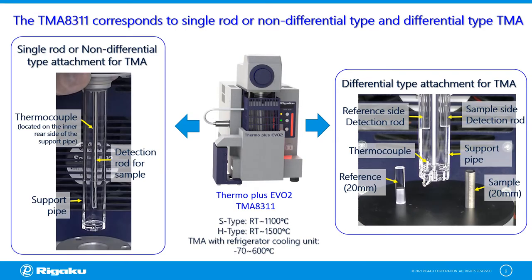The TMA 8311 corresponds to the single rod or non-differential type TMA and differential type TMA. In the differential type TMA, you can find a support pipe or support tube and two detection rods — one is for the sample and the other one is for the reference material. Both attachments can correspond to sample lengths of 10 to 20 mm. In the next two slides, each of these measurement principles will be explained.